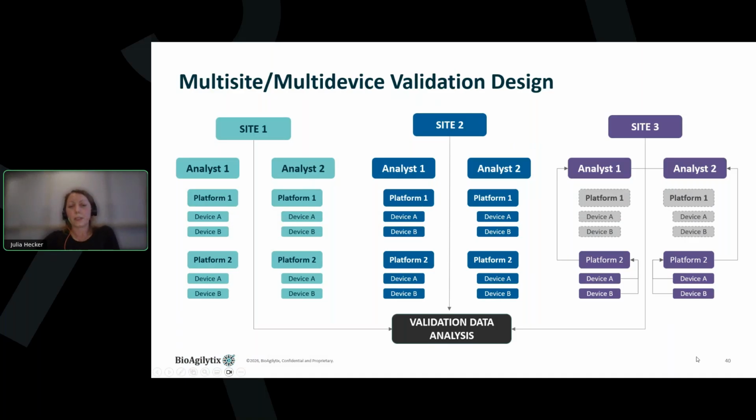Because this is also connected with the risk. We did kind of a pre-validation to see, because if this fails, then of course you would not have either site validated, but of course there are ways to, in the validation plan or in this transfer plan, to minimize the risk so that you can have either site still validated. But as we wanted to really have comparison criteria in this co-validation, we went on testing, and you can see the results on the next slide.